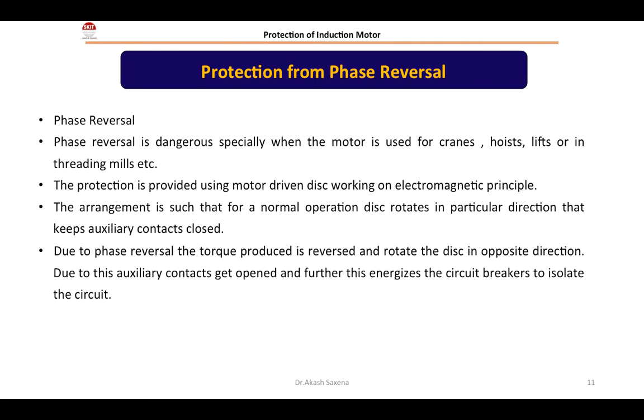But if any two lines are interchanged due to maintenance, or the phase sequence reverses, say to YRB, then the direction of the rotating magnetic field is reversed. So the motor will start rotating in the opposite direction. Such a situation is dangerous when the motor is used for cranes, hoists, lifts, or in threading mills.